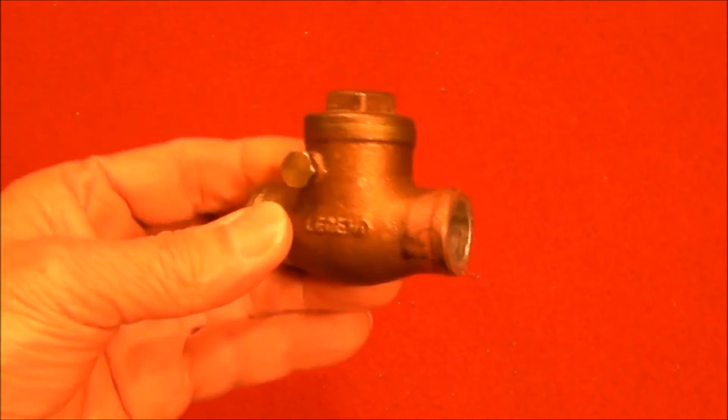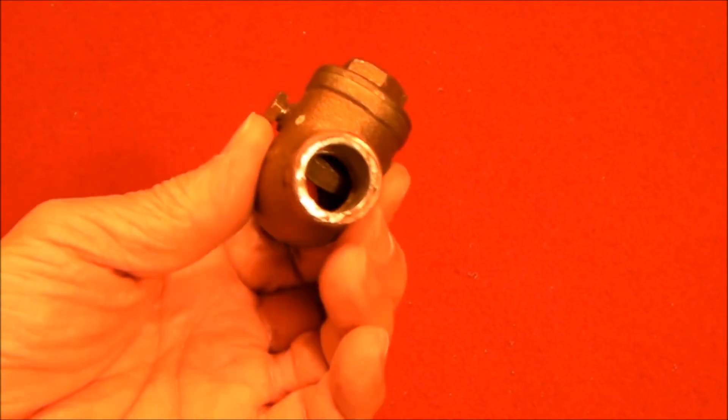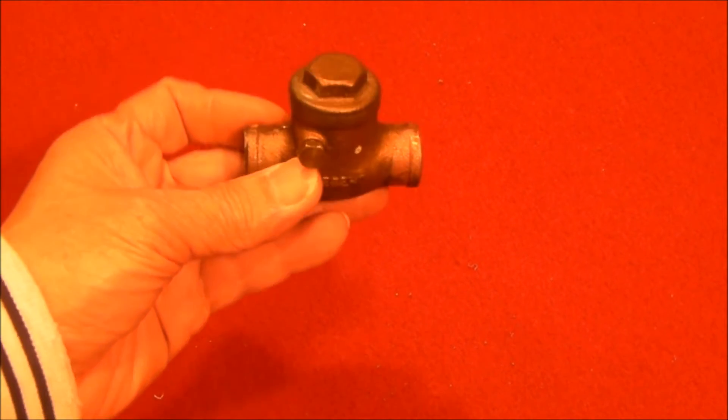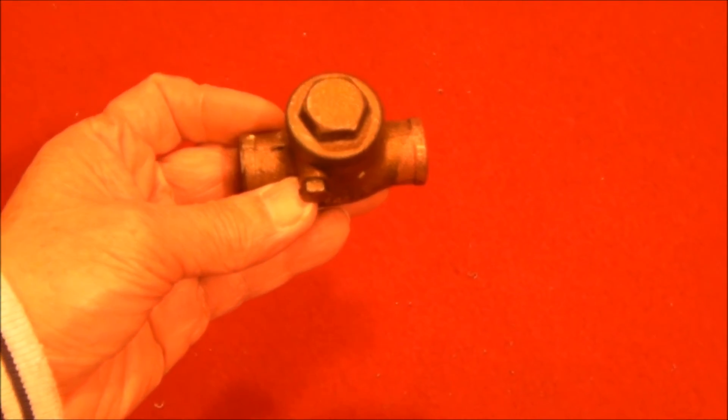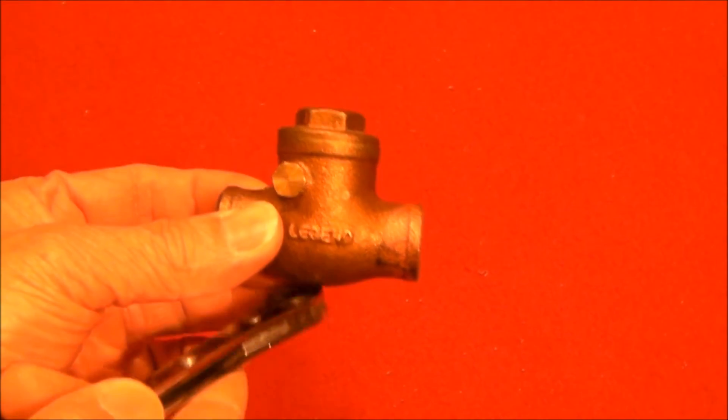Use a spring loaded one, spring loaded inline, which can be mounted in a vertical or horizontal position. As opposed to these gate check valves, which have to be mounted in a horizontal position, sort of like this, this side down.